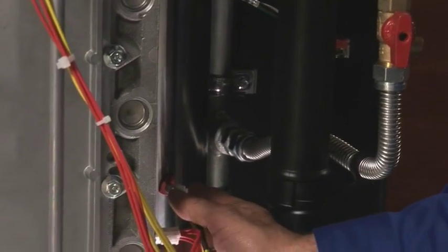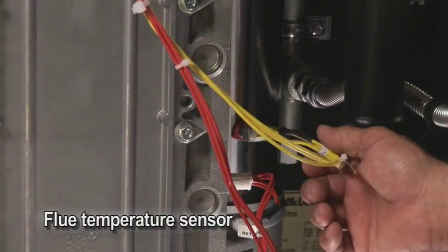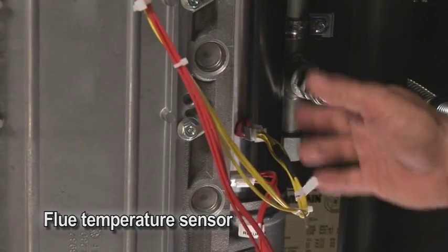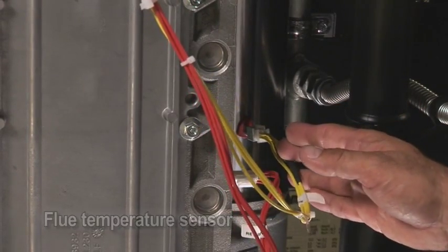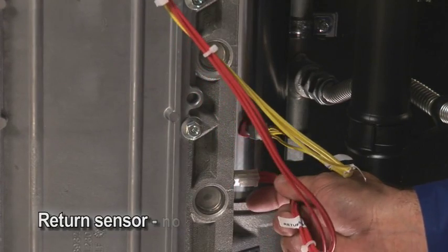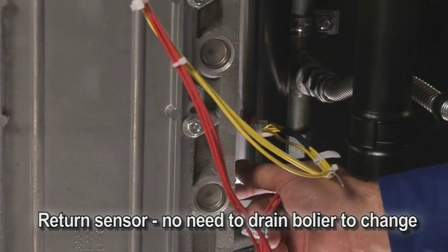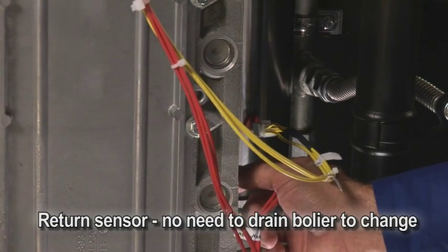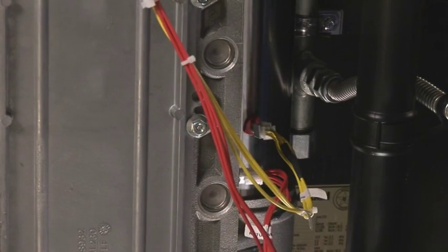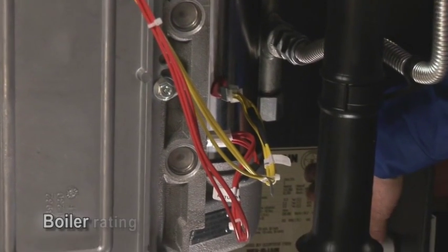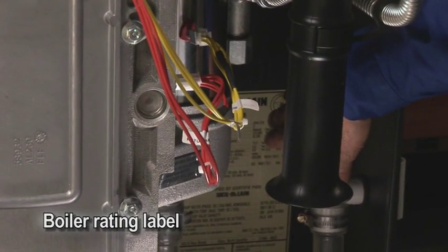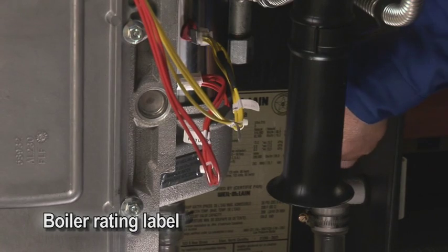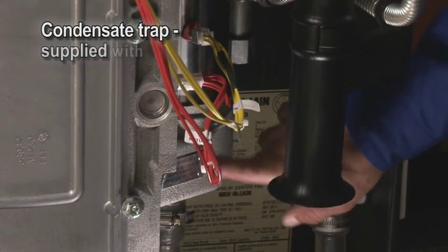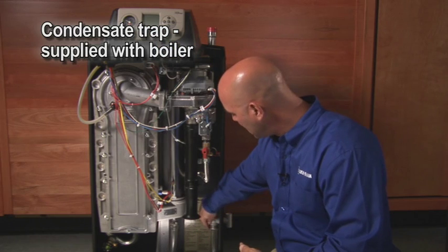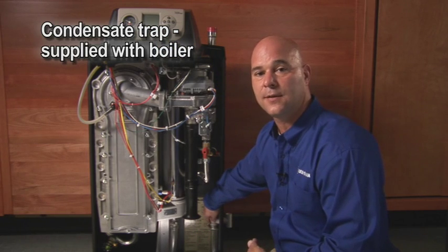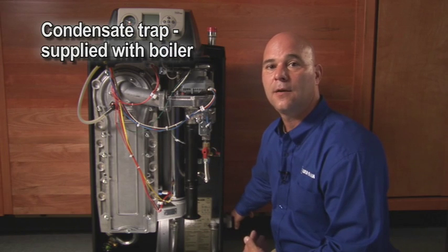Over here we have the exhaust sensor. This plugs directly into the stainless steel exhaust port going up the side of the heat exchanger. This is the return sensor. This also screws directly into the block. You do not have to drain the boiler to change this sensor either. Back here is the sticker for the boiler. It tells you the size, everything about the boiler, the input rates, the output rates. The condensate line comes off of the lower portion of the exhaust, comes up, out, and through the cabinet. All the material that you see here, including the plastic fitting, are included with the boiler.